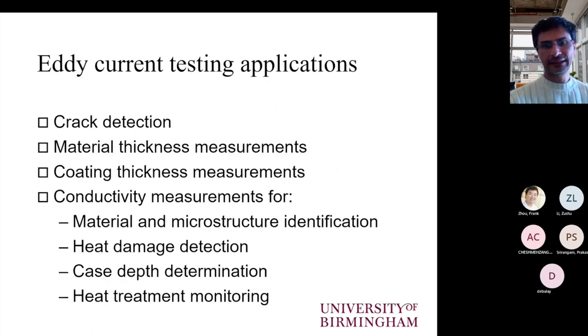The typical eddy current testing applications include, of course, crack detection. It can be used for corrosion detection as well, and pitting corrosion. Material thickness measurements, which are related to corrosion, erosion, as well as for geometrical analysis. Coating thickness measurements. So, for example, in steel turbine blades, we have special thermal barrier coatings that it is almost impossible to inspect in some cases.